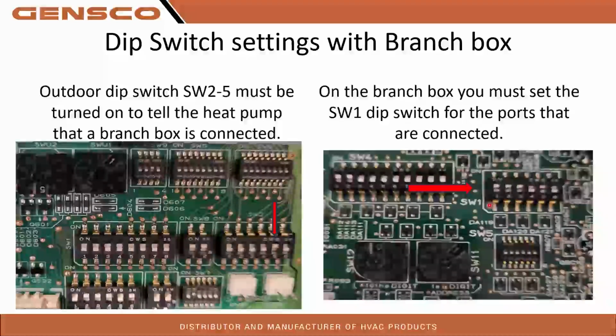On your branch box, there are some dip switches in there that you will need to set as well. So you can see our rotary dials here for our addressing. Right up next to that is the SW1 dip switch bank. What this is, is dip switches for your port assignments. So you're telling the branch box which ports on that branch box are being used.